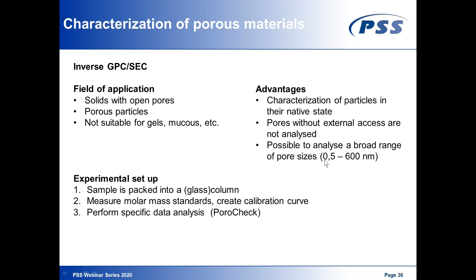For which samples can inverse GPC SEC be applied? It can be applied for all solids with open pores, for all porous particles. However, it's not suitable for gels, for example. The advantage is that you characterize your particles in their native state with just general LC equipment, with normally non-toxic solvents. You don't have to use other techniques, and it's possible to cover a very wide pore size range from 0.5 to 600 nanometers.